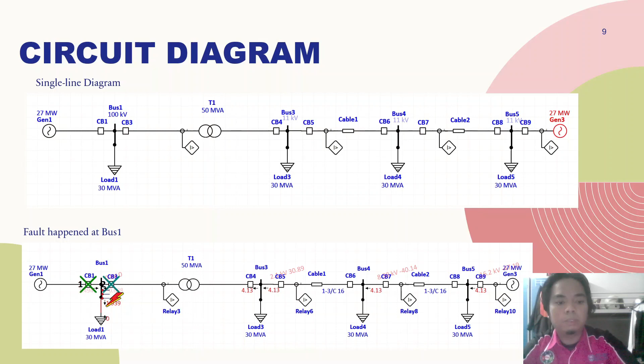The type of relay that we use in this project is Inverse Definite Minimum Time (IDMT) overcurrent relay. For the calculation, first we need to find the full load current with the formula: transformer in MVA over root 3, multiplied by the voltage.